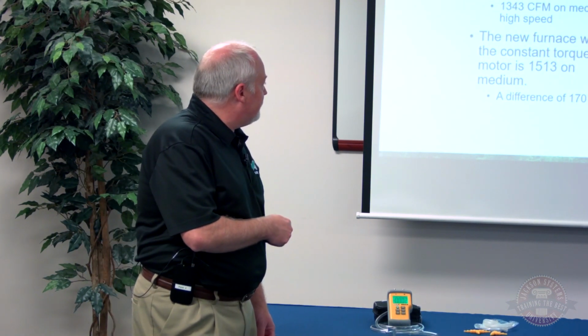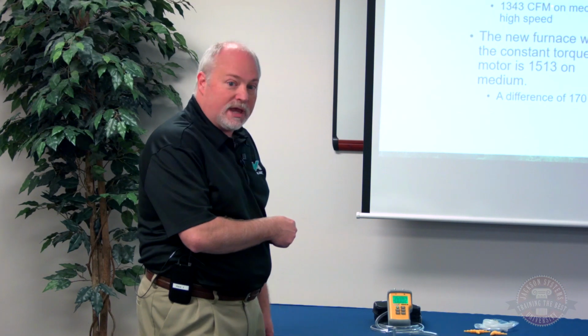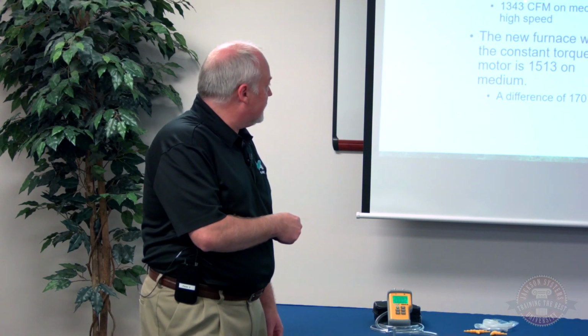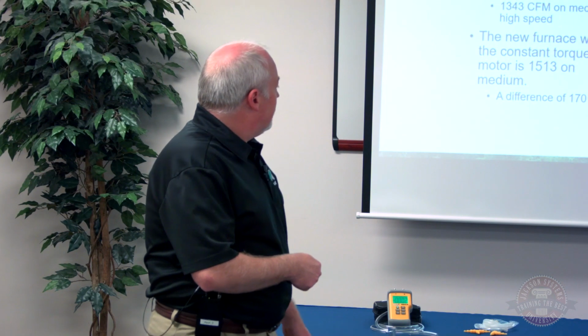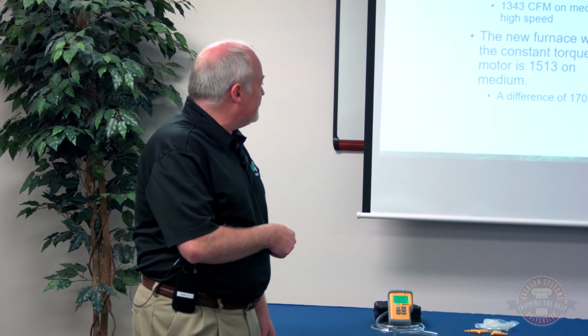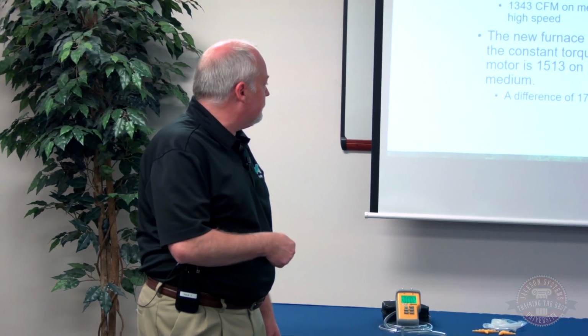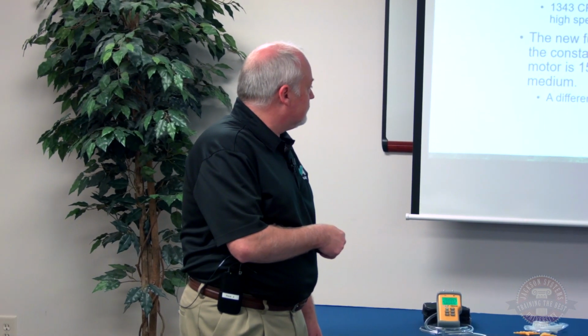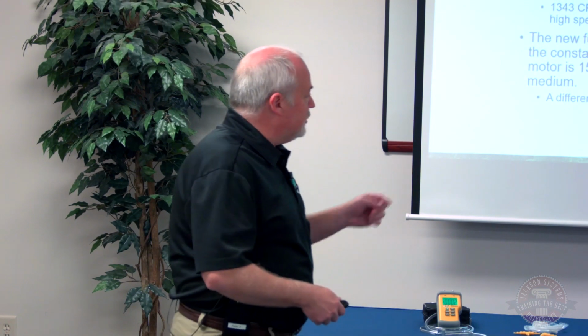So I've got a 75,000 BTU furnace in both cases. This case, it has what they referred to as a 4-ton blower, because it can do up to 1,600 CFM. Kind of a rule of thumb is 400 CFM per ton. If we pull that out and put in this new furnace that moves 1,513 CFM, that's a difference of 170 CFM. So we may have a situation that, hey, that duct system can be a little noisy now because we're moving more airflow through that duct. So that's something that we can use to determine.